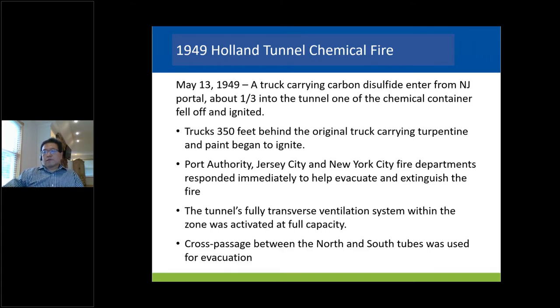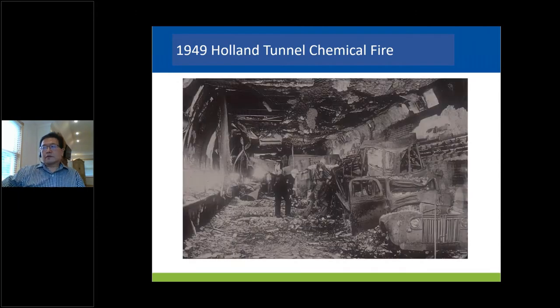The tunnel has what they call a fully transverse ventilation system, and they activated it at full capacity, which helped dilute the smoke and enable the firemen to go in and put out the fire. They also used the cross passages between the north and south tubes in the tunnel, so people from the tunnel where the fire is can cross over to the other tunnel for temporary safety.